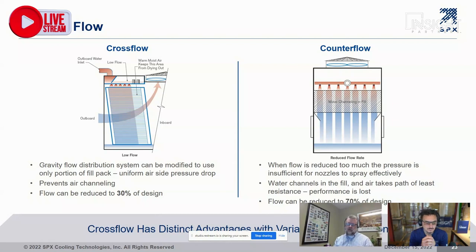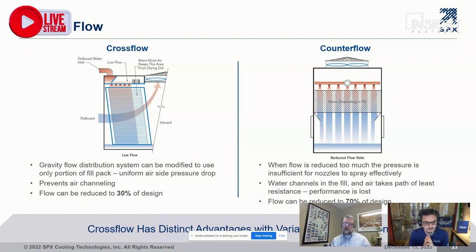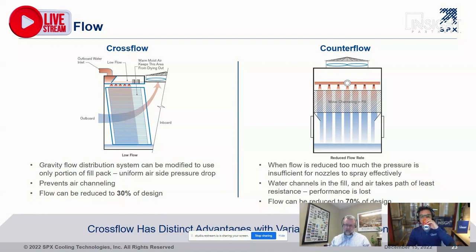The methodology to handle lower flow rates across all available cells is to use what we call nozzle cups, placed into the cooling tower distribution basin. These allow lower flow rates while maintaining adequate water distribution on the outboard edge, ensuring uniform air-side pressure drop, minimizing scale, and minimizing icing. In a crossflow arrangement, water is distributed on the outboard edge while the inboard edge — where the air is nearly saturated — gets less water, avoiding icing and scaling concerns in that region.